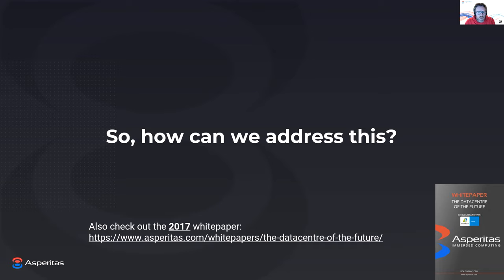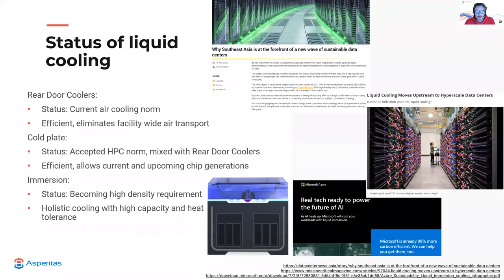Everybody in the industry is now familiar with at least a concept of liquid cooling, but still only a handful are actually using, deploying, and scaling with liquid cooling. The most well-known form of liquid cooling now relates to rear door coolers. These are water-cooled heat exchangers, which act as air handlers at the rear door of the rack. These are efficient and eliminate the need for facility-wide air transport. These are currently the new norm for air cooling and are integrated in the new OCP rack definitions. Cold plate is mostly applied in the HPC and supercomputing environments, while now becoming an occasional add-on for mainstream systems. Full cold plate racks are often equipped with rear door coolers because cold plates only cool the most essential and hottest chips in the rack.